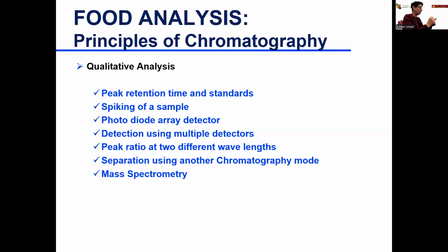So with the photodiode array detector, you get a fingerprint for the compounds, and you can identify the compounds based on their absorption. So it kind of gives you three-dimensional data. At every fraction of a second, you get a spectra. So that's very powerful. It has its limitation, but it's very powerful in detection.